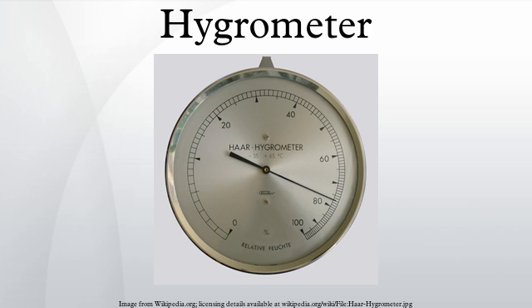Psychrometers. A psychrometer consists of two thermometers, one which is dry and one which is kept moist with distilled water on a sock or wick. The two thermometers are thus called the dry bulb and the wet bulb. At temperatures above the freezing point of water, evaporation of water from the wick lowers the temperature, so that the wet bulb thermometer usually shows a lower temperature than that of the dry bulb thermometer. When the air temperature is below freezing, however, the wet bulb is covered with a thin coating of ice and may be warmer than the dry bulb.